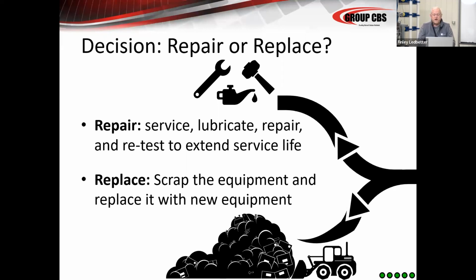The problem with scrapping it is disturbing the cables. Can you get in there? Can you get in the place to replace it with new equipment? Have you built around it to the point where you don't have good access any longer? When a lot of these switchgear rooms are built, there's a nice big roll-up door on the end, but now maybe outside that door there's been a buildup. Maybe the door's been replaced with a block wall over the years. There's a big heater there. There's a big furnace there, whatever. 50, 60, 70 years ago, all that was considered, but now you've built up around the gear and it's tough to get out.